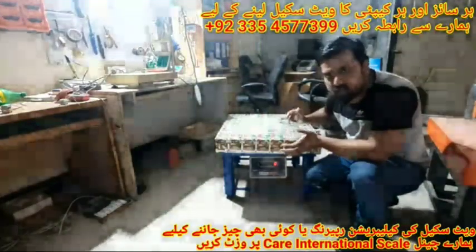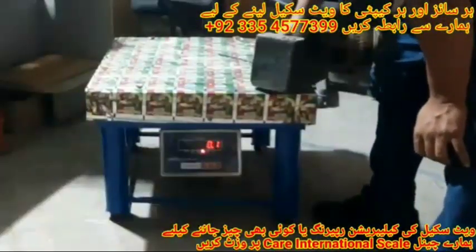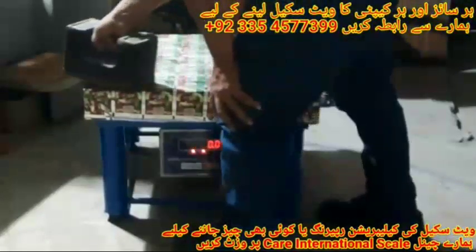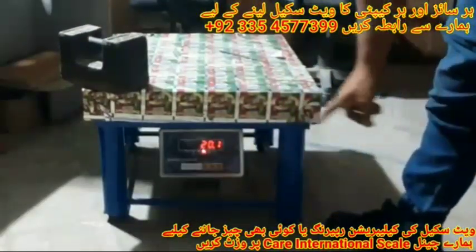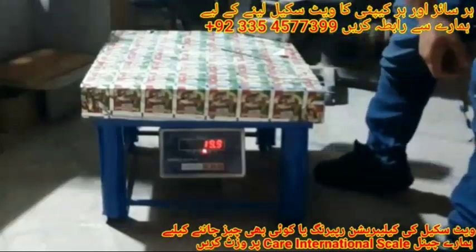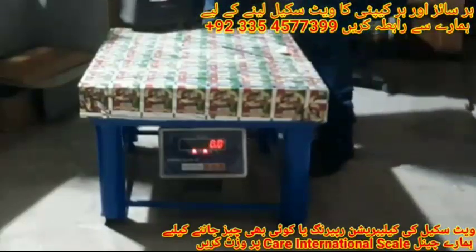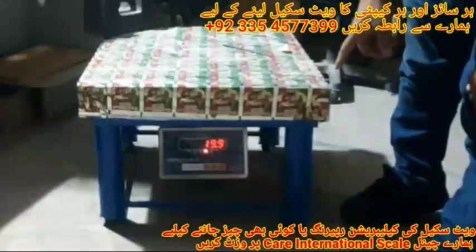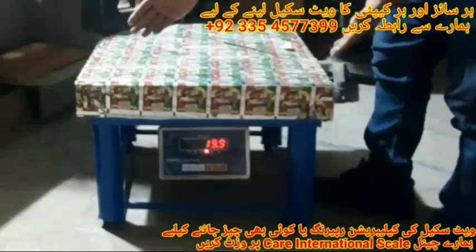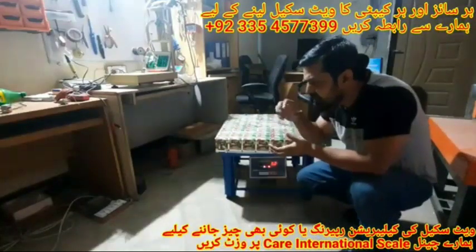We have a 20 kg dead weight. We will place it in all four corners of this platform and check whether it is giving correct weight or not. In the first corner it's showing 20.1 kg. In the second corner it is showing 20.1 kg. In the third corner it's showing 19.9 kg, and in the fourth corner it is also showing 19.9 kg. So the weight of the first and second corners is the same, and the weight of the third and fourth corners is the same.